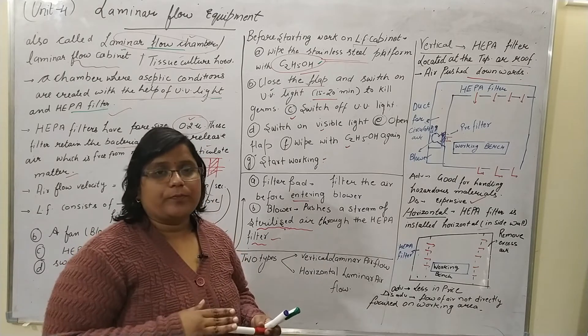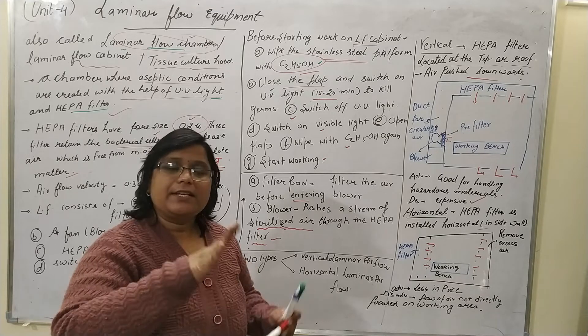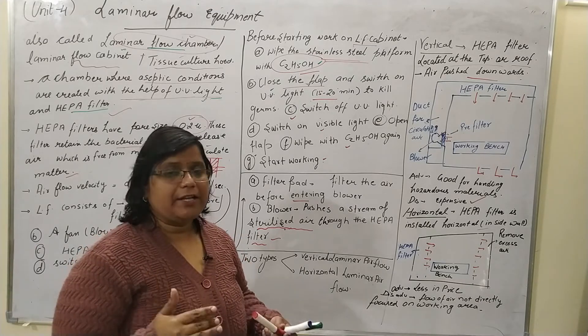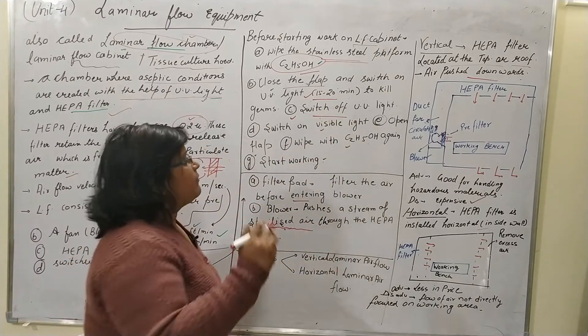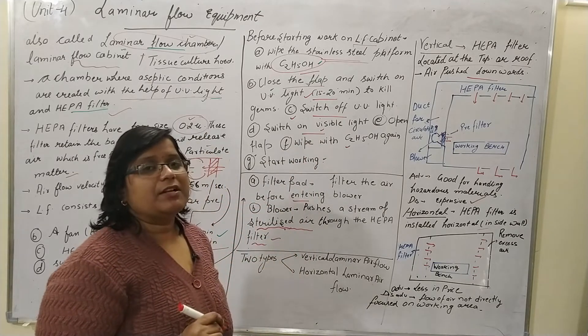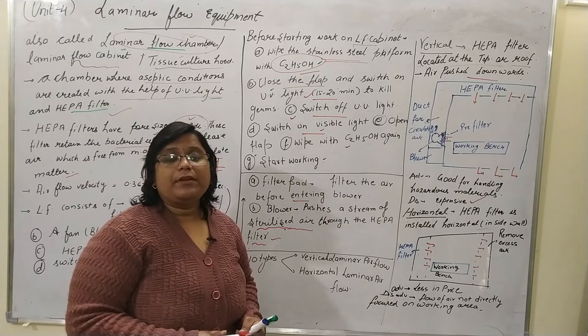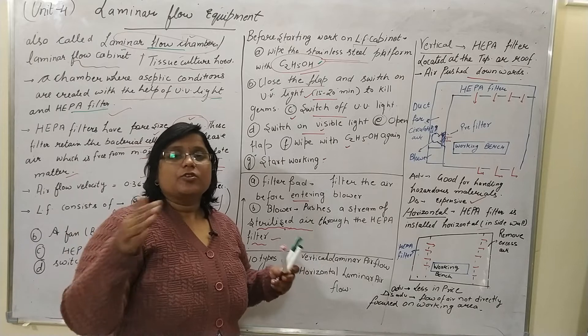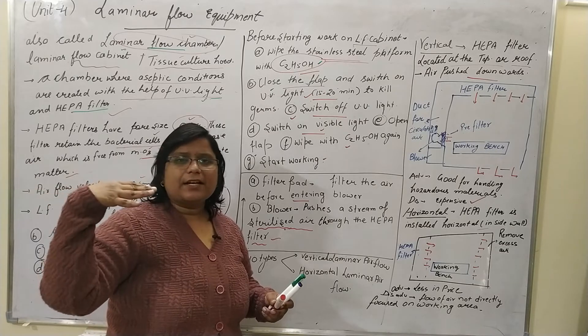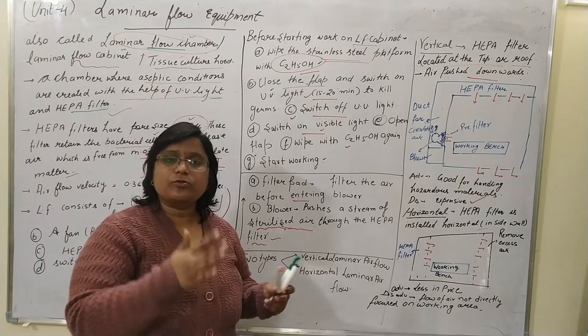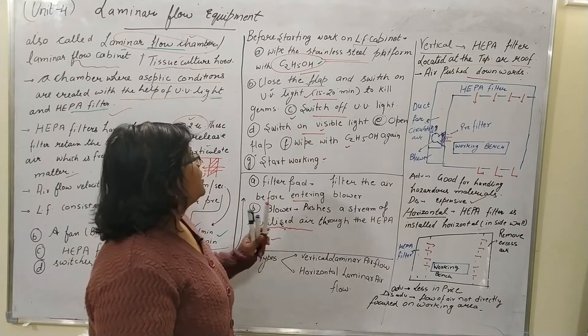UV light is harmful for microorganisms but also harmful for you, so just switch it on and keep away. After 15 to 20 minutes, switch off the UV light, then switch on the visible light. We switch on the visible light because the laminar airflow cabinet is covered on three sides, making it quite dark inside — the visible light works like a simple tube light.